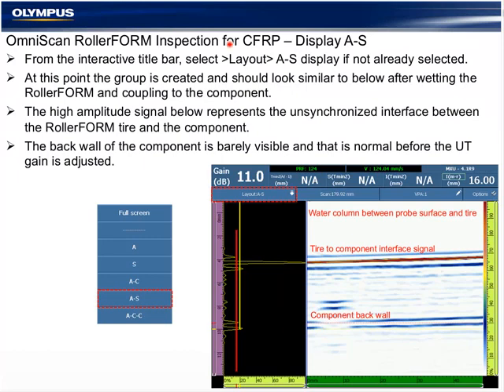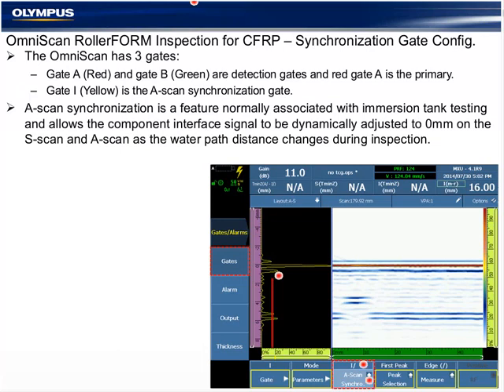It's normal that the yellow gate disappears when we're in A-scan synchronization mode because it's dynamically updating for every A-scan to build the S-scan display, similar to an immersion tank. And as we can see, once we enter A-scan synchronization mode, the yellow gate disappears and my interface signal is completely flat and straight and automatically aligned at 0 millimeters. This is a very important feature for either a RollerFORM or an immersion tank, as it allows precision measurements inside the C-scan to be relative to 0 instead of relative to the distortion of the probe in the tank or the RollerFORM.